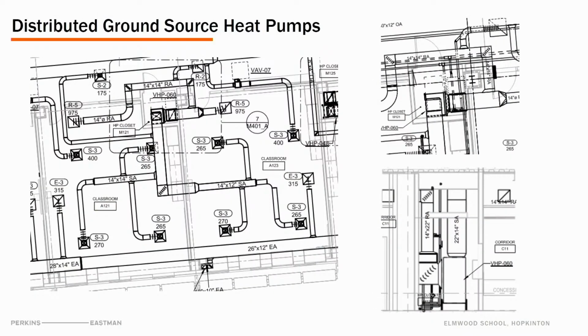But this is not this school, this is another school we designed with Perkins Eastman that shows one heat pump per 2 classrooms. You can see right here, that's the heat pump in the closet. The closet accesses off the corridor so that if Tim has to work on it, he doesn't have to get into the classroom environment to take care of it, which is another little bonus feature we like. Then we have ductwork that distributes air to both classrooms, and we gang classrooms together that have common exposure and common occupancy. We're not going to mix an office and a classroom, we're going to mix a second grade classroom with a second grade classroom, and they tend to go around in groups anyway, so that zoning works well. We do that to help reduce equipment, because it would be crazy to put one in for every classroom, it's already a lot of equipment, so we try to balance the amount of equipment we're buying that we have to maintain. So we'll zone that accordingly, that's what that looks like.